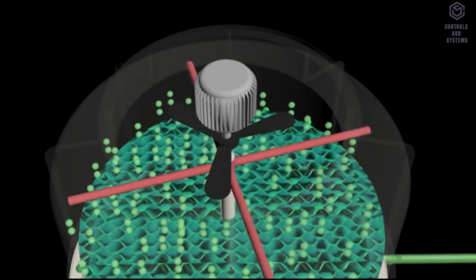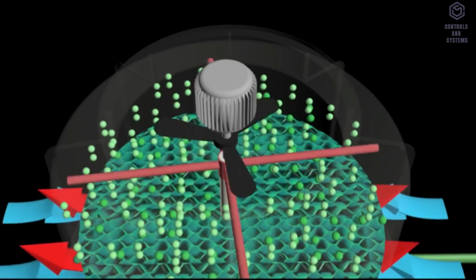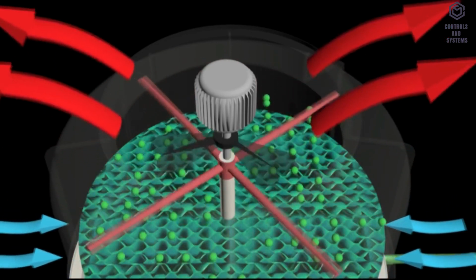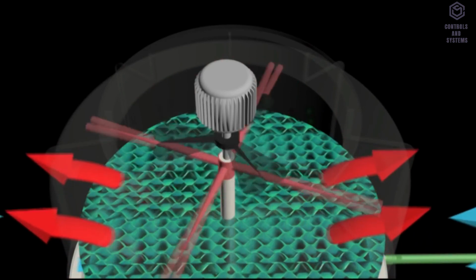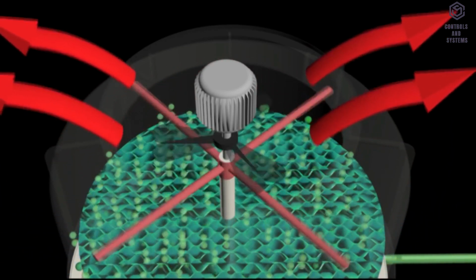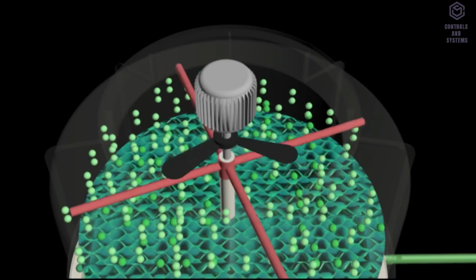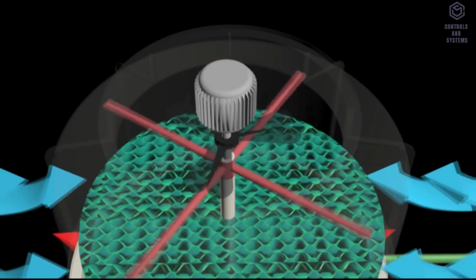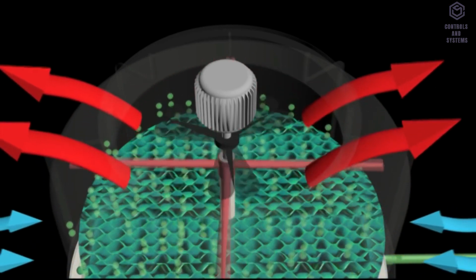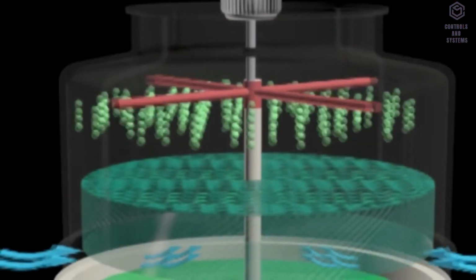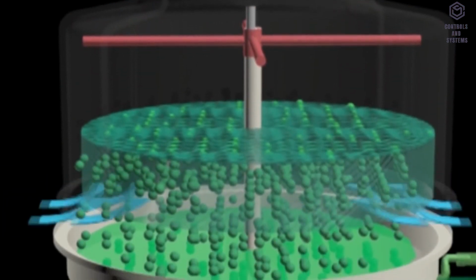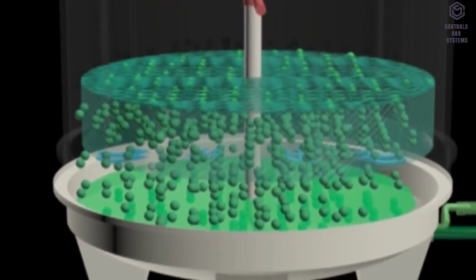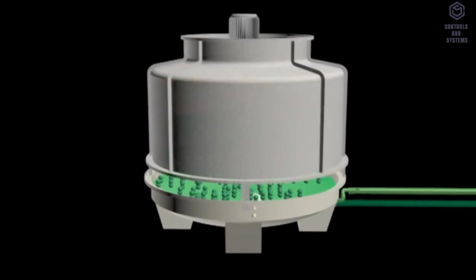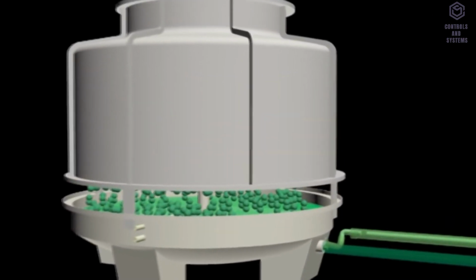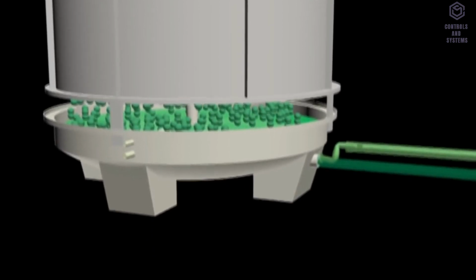the fins. Air through the fins is drawn by a rotating fan on the sprinkler blade, rotated by the motor. This fan rotation causes the air to move from the bottom to the top of the cooling tower, which is opposite to the flow of the condenser water. Condenser water, which has had its heat eliminated by the surrounding air, will accumulate in the basin under the cooling tower. Condenser water that flows out from the cooling tower to the chiller is called condenser water supply.